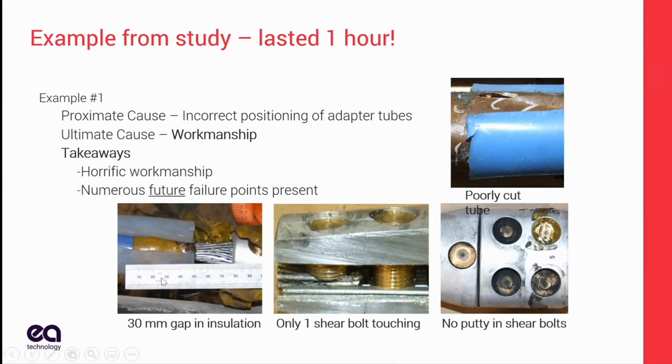The failure occurred mainly because of this 30-millimeter gap between the end of the insulation and the barrel of the joint. You had discharge raging that caused a flashover. You didn't need much partial discharge. It almost flashed over on energization. But that was just one cause.